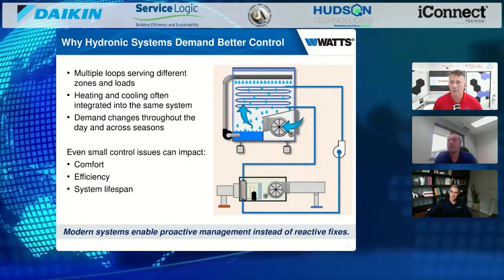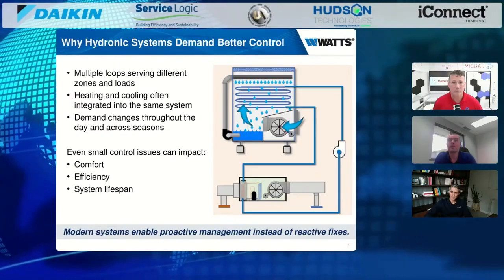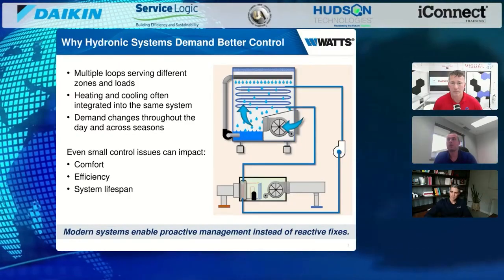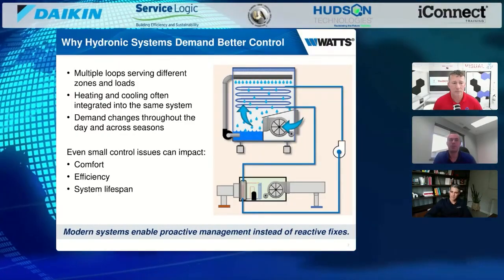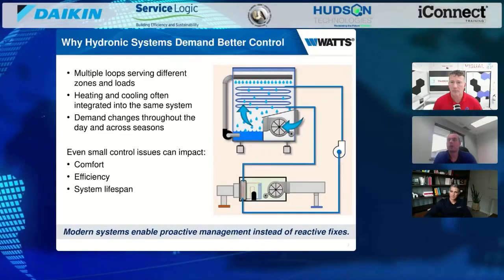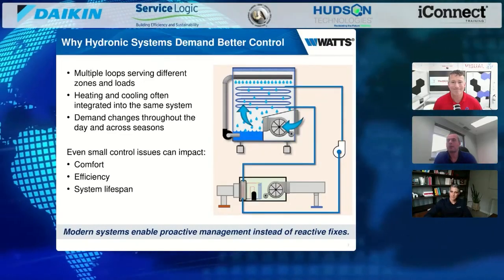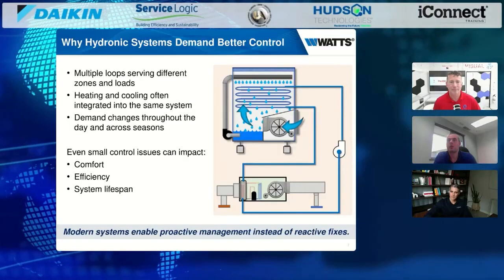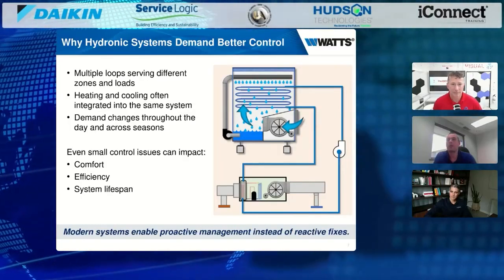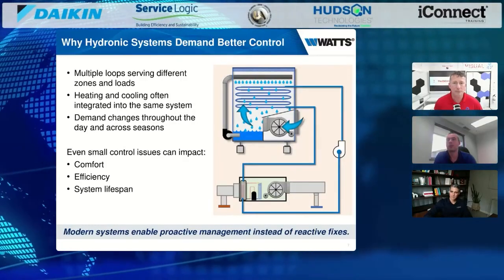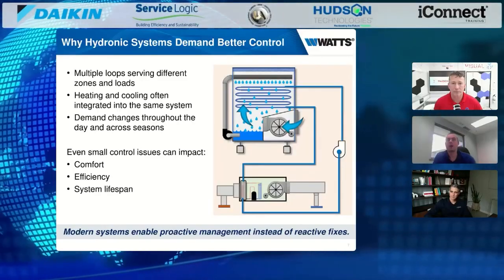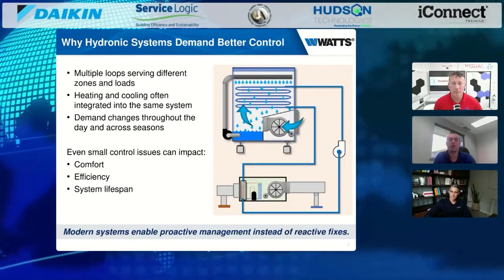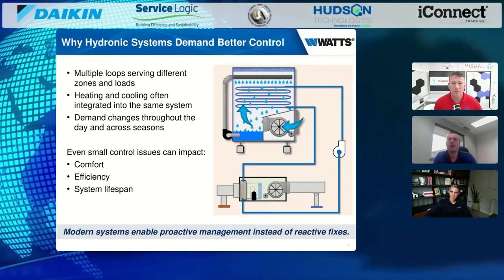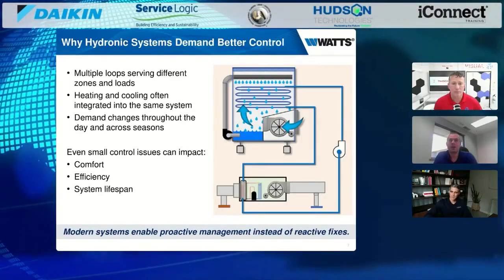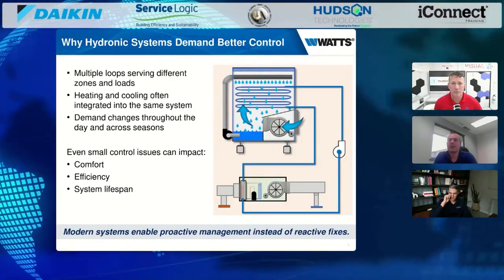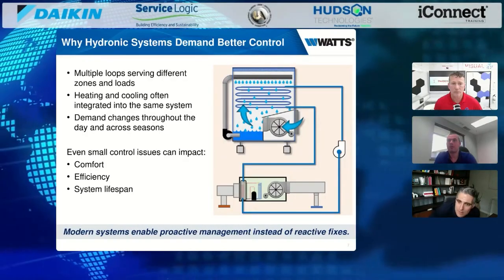And the advanced controls are also optimizing the plants for this, the chillers and the boilers and the heat pumps, reducing short cycling. They're optimizing the runtime, making sure you can cycle between equipment if you have multiple sources of heat or cooling, so you're not wearing one out 5 years earlier than the other. These advanced controls just allow you to have this level of control that can adapt with the dynamic nature of a building.